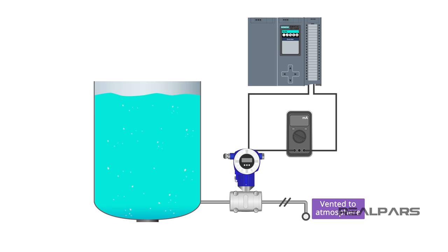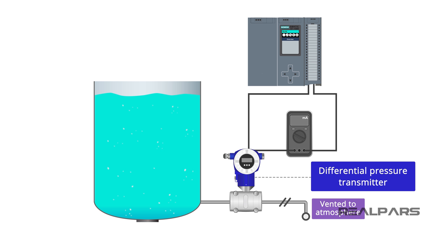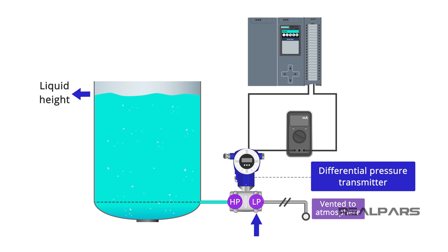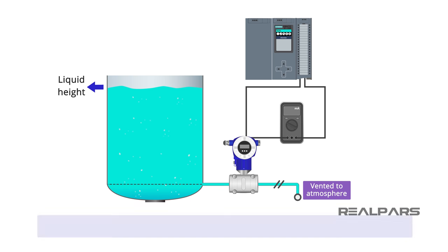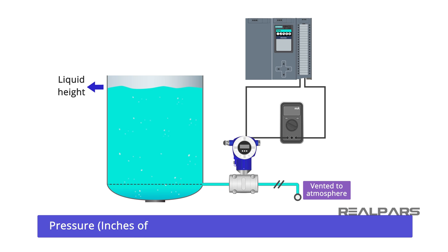As a refresher, let's look at how we ended the first part of this video series. We looked at a control loop where a differential pressure transmitter is connected to measure an open vessel level. The high pressure port is connected at the 0 inches point, and the low pressure port is vented to atmosphere. Pressure in inches of water is equal to the relative density of the liquid multiplied by the height of the surface of the liquid in inches.